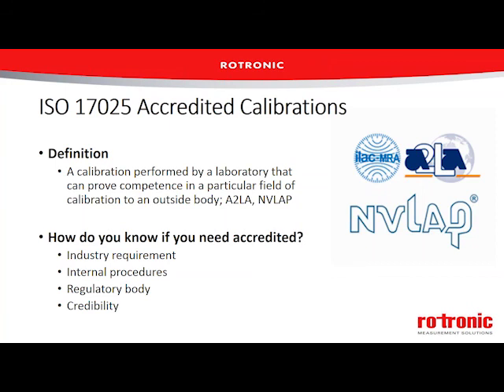17025 is slightly different than 9001. 17025 is an accreditation to prove the competence of a laboratory. So essentially a laboratory that has become accredited to a particular parameter has proven that they're competent to perform that calibration and that they can actually achieve the uncertainties that get reported on the calibration certificate. And this is checked in a couple different ways.